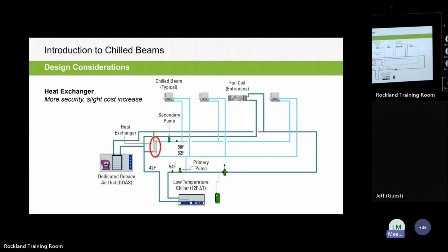And then quite similarly, maybe more security with this type of heat exchanger, but you've got the plate and frame heat exchanger that's introduced where that mixing valve was to provide that energy transfer and the warming of the chilled water loop for the chilled beam.